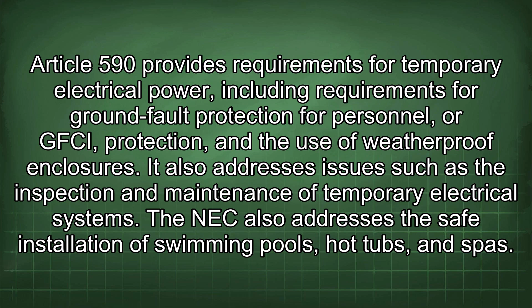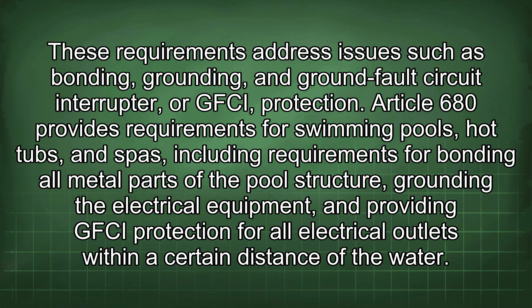The NEC also addresses the safe installation of swimming pools, hot tubs, and spas. These requirements address issues such as bonding, grounding, and ground fault circuit interrupter, or GFCI, protection. Article 680 provides requirements for swimming pools, hot tubs, and spas, including requirements for bonding all metal parts of the pool structure, grounding the electrical equipment, and providing GFCI protection for all electrical outlets within a certain distance of the water.